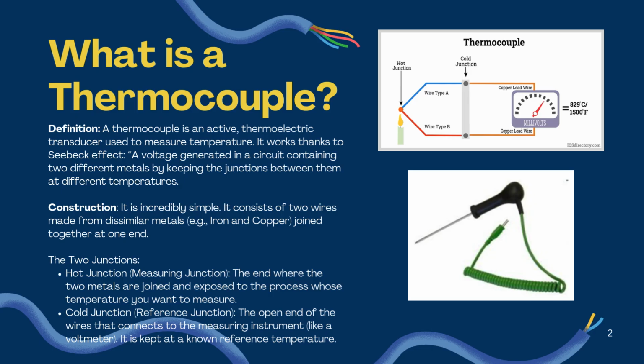So how do you build the thermocouple? It is incredibly simple. It consists of two wires made from dissimilar metals, which are two different metals such as iron and copper, which are joined together at one end. There are two junctions for the thermocouple. One is the hot junction for measuring the voltage, and another one is the cold junction, which is a reference junction.